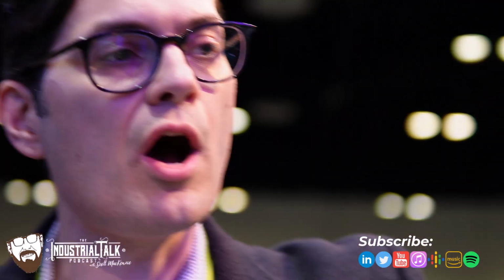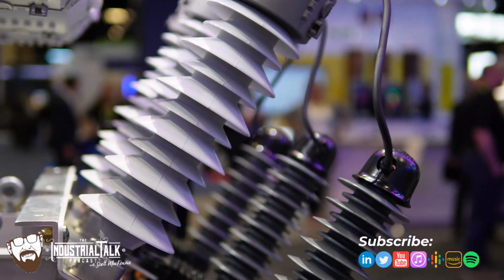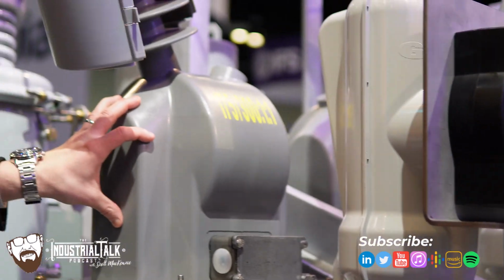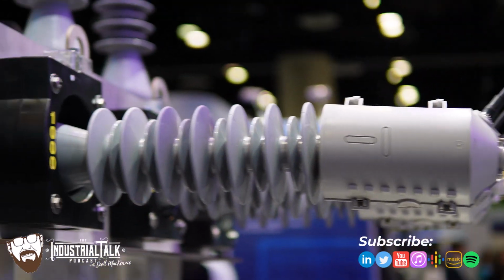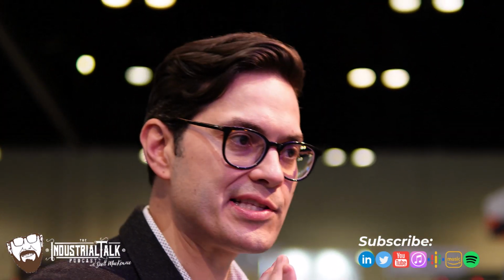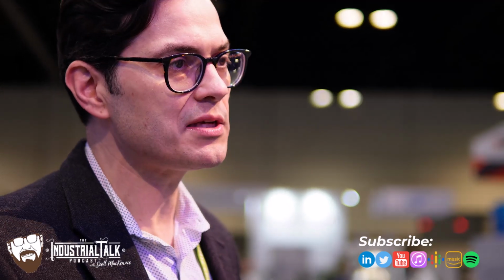Data's everything. So let's keep on that data theme, right? So we're talking about primary metering here, but we also have the ability to add very high accuracy, capacitively coupled voltage sensors. Right. This is capacitively coupled. These are inductor-based transformers. These guys are extremely accurate, 0.5% accuracy on voltage, but they have amazing resolution on harmonics. Now renewables are a wonderful thing, right? Yeah, but lots of green energy. It's something that we want as a society, but the thing that doesn't get talked about a lot is renewables are a real pain to integrate into the grid.